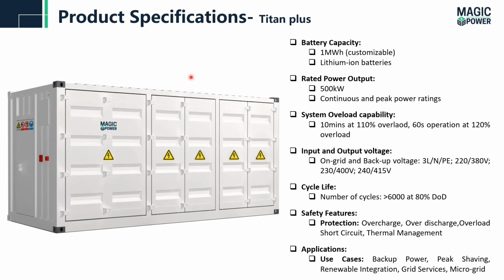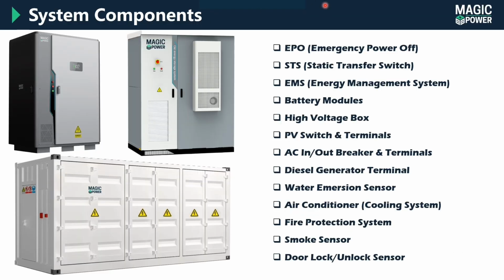Next we look at what main components we use in the system for safety and operation, such as sensors and protection systems. The system components include the emergency power off button, transfer switches, and the energy management system, which manages the energy we want to buy from the power grid or the energy the solar power generates. Similarly, there are the battery modules, high voltage box, and switches for solar panels, power grid, and load side diesel generator terminals. As for sensors, since the system is outdoor, it has water immersion sensors, and the cooling system is an air cooling system, with a fire protection system, smoke sensors, and a door lock and unlock system. Sensors are installed in the system.